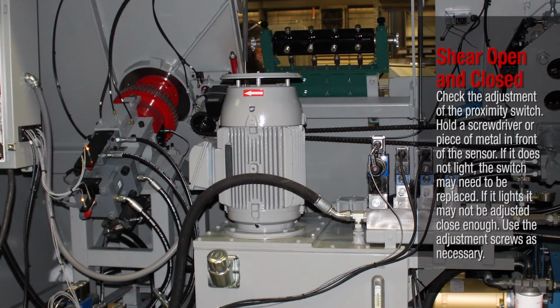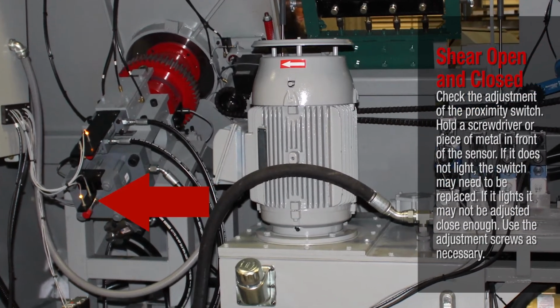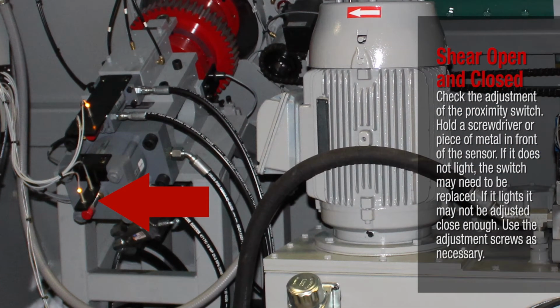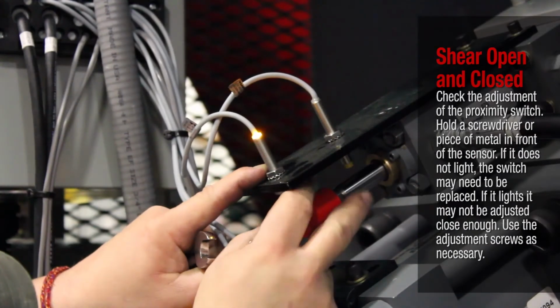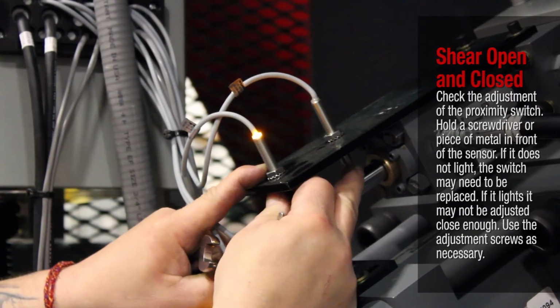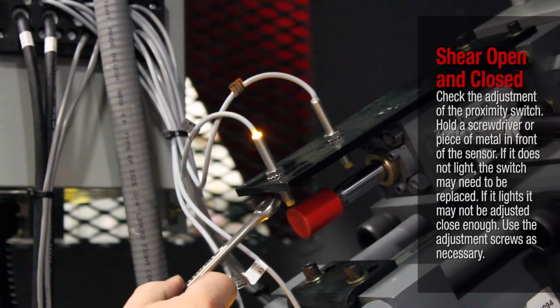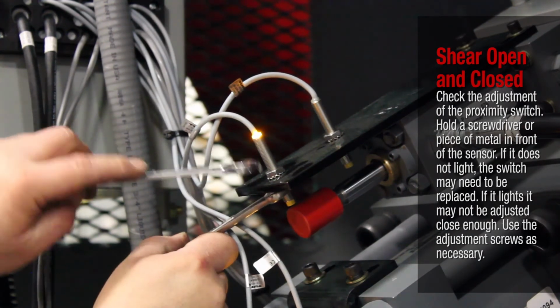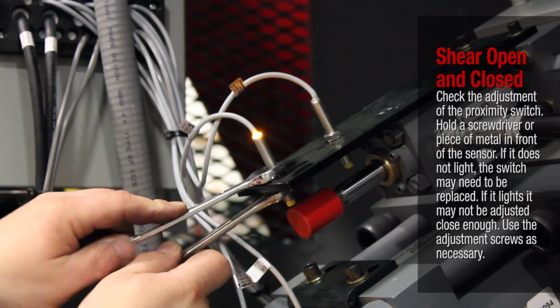Shear open and closed. Check the adjustment of the proximity switch. Hold a screwdriver or piece of metal in front of the sensor. If it does not light, the switch may need to be replaced. If it lights, it may not be adjusted close enough. Use the adjustment screws as necessary.